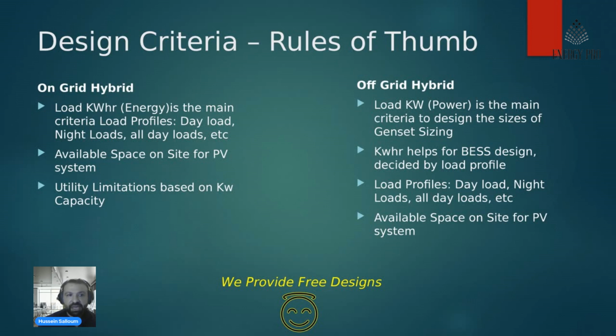On the other side, the off-grid system has to take care first of the power, not the energy consumption. Because here you have no grid, you need to take care of the load capacity, the maximum load capacity. And here you start with the kilowatt, not the kilowatt hour. So this is the main criterion in the design. First, for the generator, you have to have the generator covering the full size of the power, because it has to act as the voltage source, as we said before.